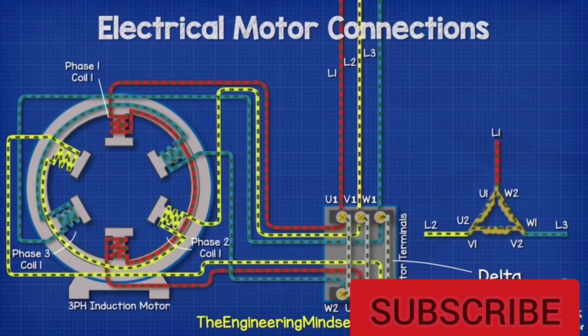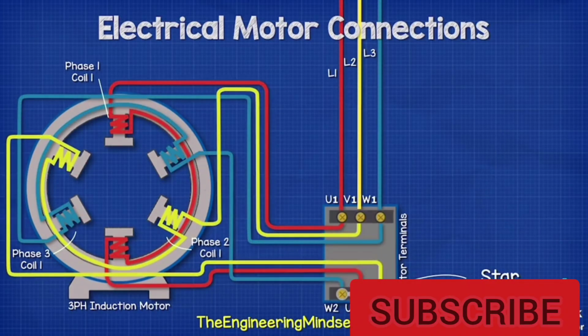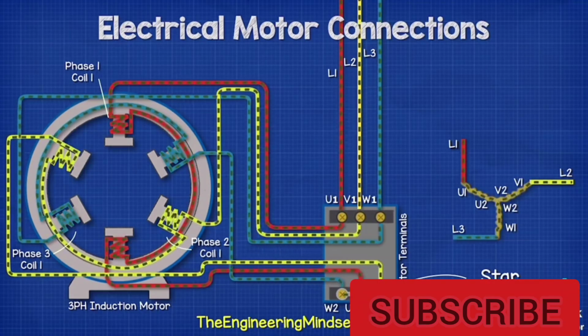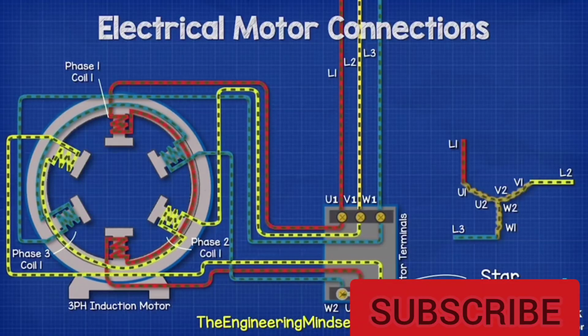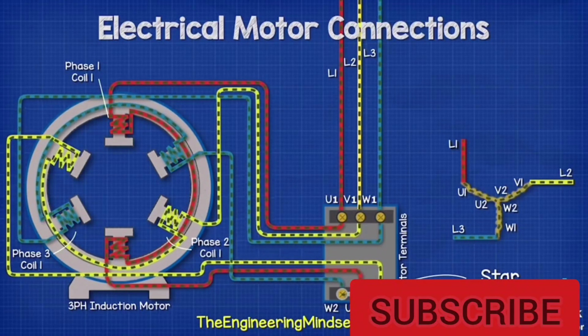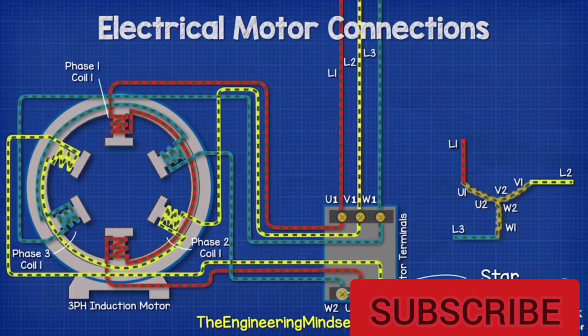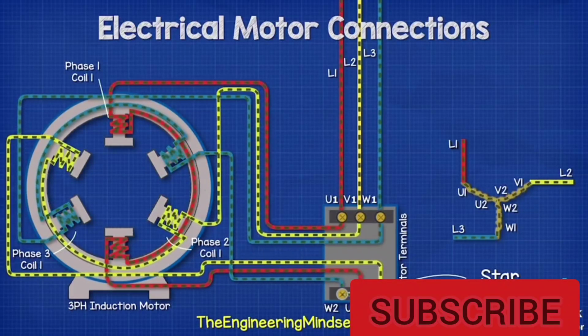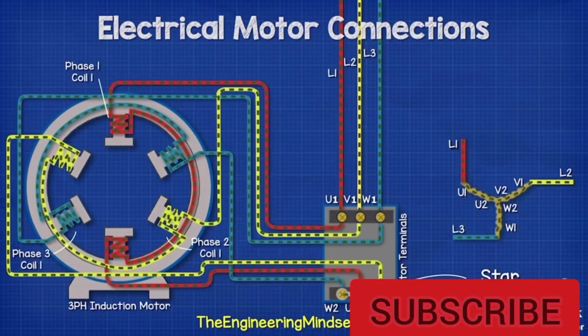The other way we can connect the terminals is to use the star or Y configuration. In this method, we connect between W2, U2 and V2 on only one side. This will give us our star or Y equivalent connection. Now, when we pass electricity through the phases, we see the electrons are shared between the terminals of the phases.